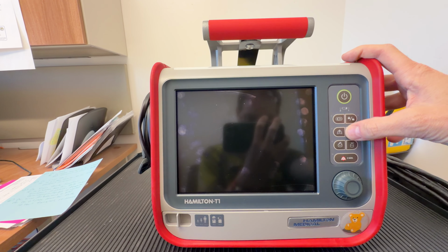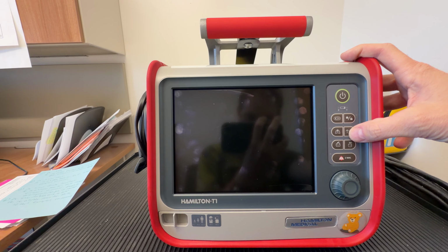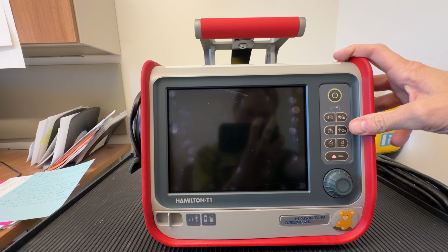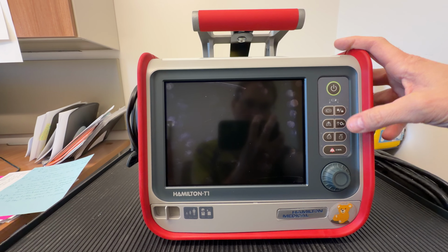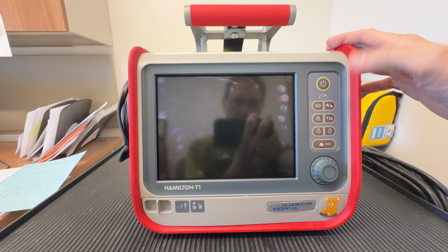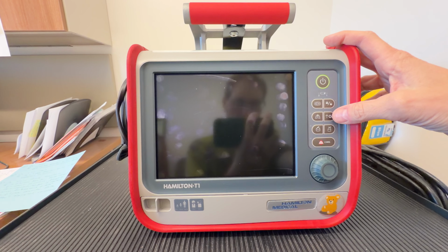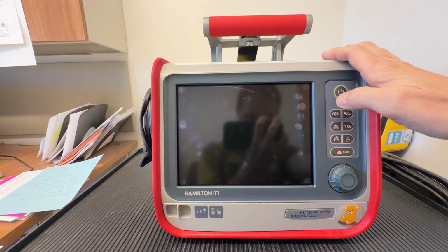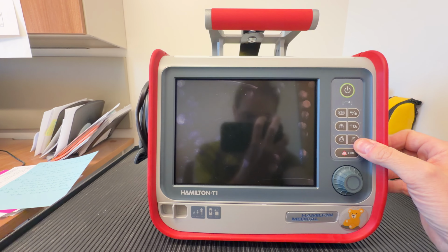This little O2 here is what's referred to as the oxygen enrichment key. You hit this and it'll essentially pre-oxygenate the patient on 100% FiO2 if you have oxygen going into the ventilator, and it'll do that for 2 minutes. This next little button here, this little printer, this is the print screen. You can hit this, and it'll take a screenshot, and then I'll show you where the adapter is. If you have a USB flash drive plugged into the ventilator, it'll save that to that flash drive. This button here is the nebulizer on-off.